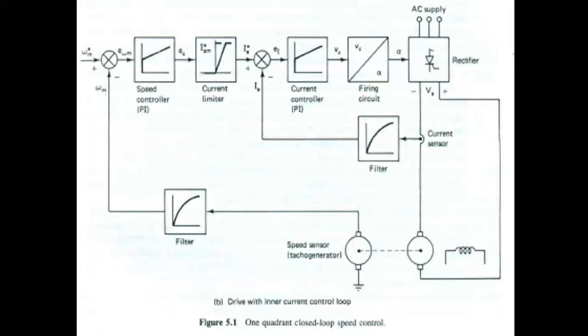A decrease in the supply voltage will reduce the motor current and torque. In current limit control, the speed will fall because the motor torque is less than the load torque, but the current reference is not changed there. The resulting speed error is brought back to the original value by setting the rectifier firing angle at lower values. The response of the drive is mainly governed by the mechanical time constant.